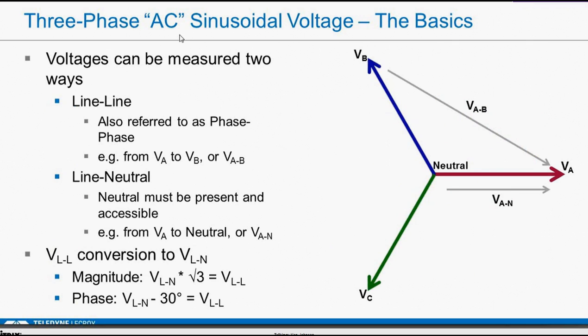All right, so now as we look at three-phase voltage measurements, here's where things get a little tricky. You can measure line-to-line or line-to-neutral. Line-to-line would be from phase A to B. Normally, it's not referred to as a vector notation. This is really just a convention. So in this case, A to B means A to B, with A being the higher, so the vector pointing in this direction.